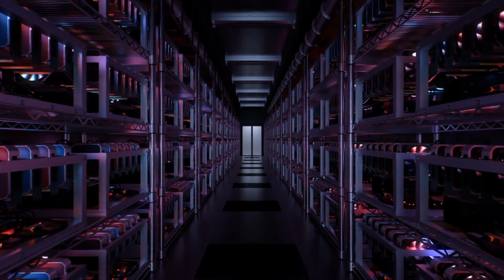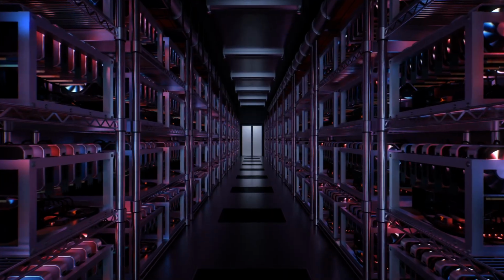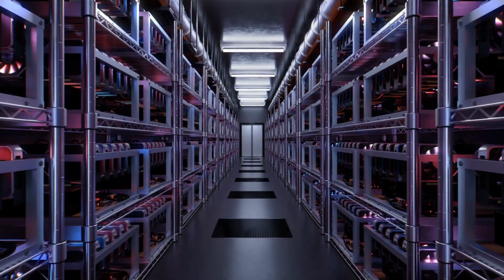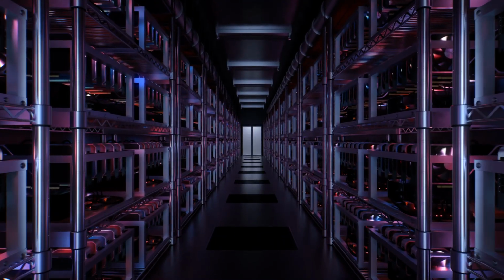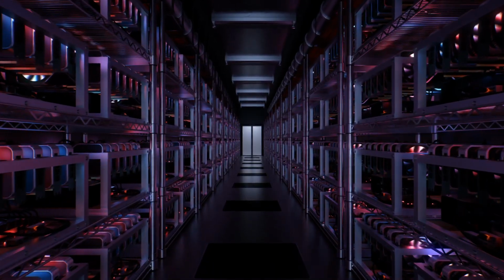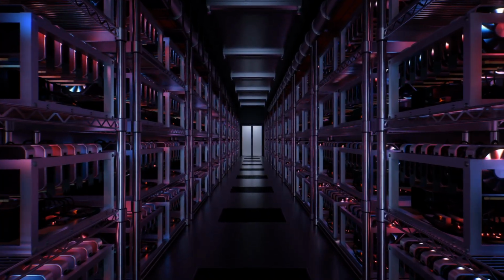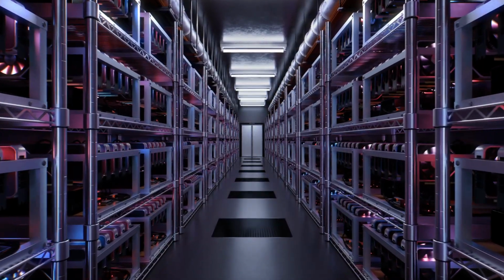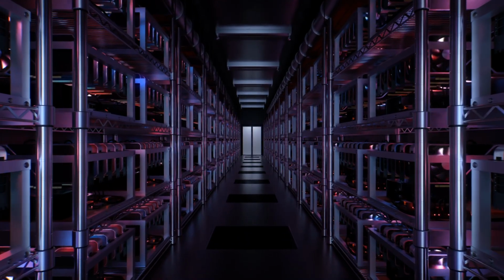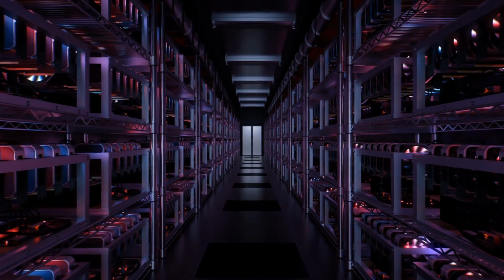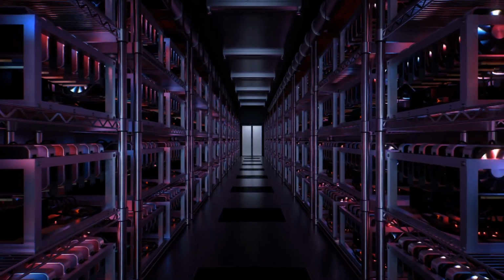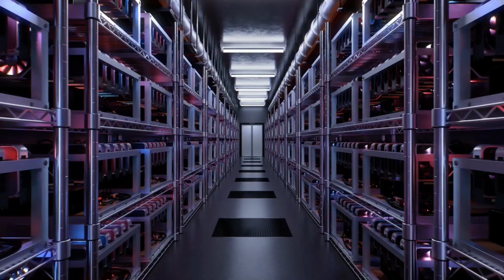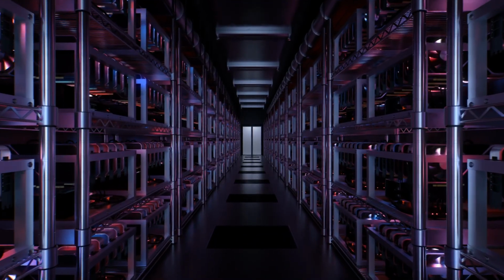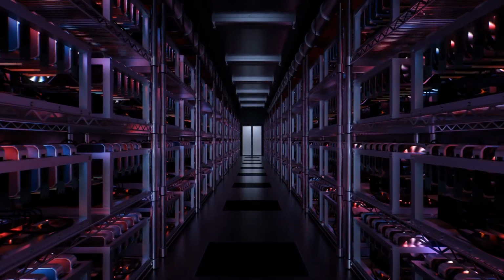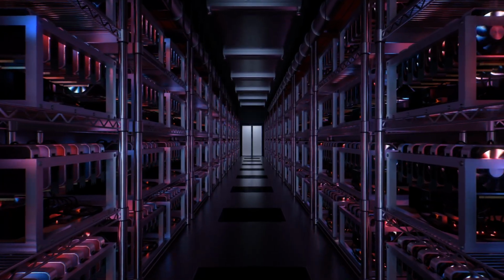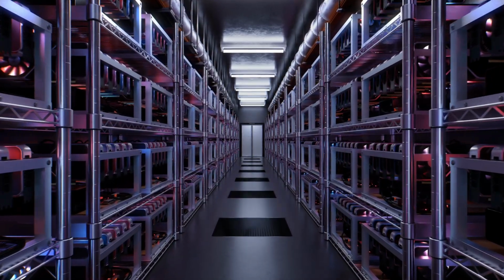If you take a glass of ice water outside on a humid summer day, the outside of the glass instantly starts sweating. Precisely. The warm air immediately surrounding that cold pipe reaches its dew point, and the moisture suspended in the data center air rapidly condenses into physical water droplets on the exterior of the pipe. And in a data center, having water magically appear out of thin air, accumulate on overhead pipes, and drip down onto electrified, multi-million-dollar AI servers. So that is an absolute catastrophe. Indoor rain in a server room is a career-ending event for a facility manager.